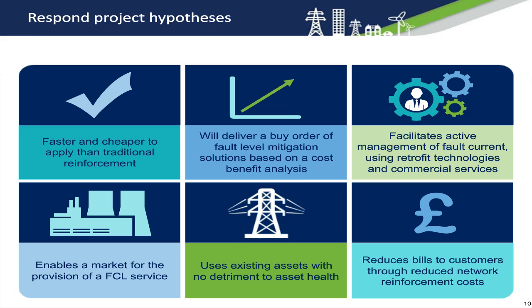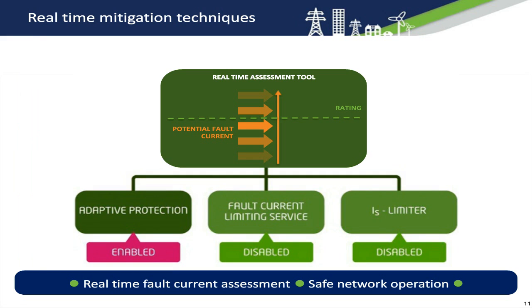When a fault level approaches or rises above the fault level rating of our network equipment, the fault level assessment tool, known as a FLAT, which is now embedded into our network management system, will enable or disable one of three innovative techniques designed to manage fault current. They are adaptive protection, the fault current limiting service, and the IS limiter. All three techniques, when enabled, respond after a fault, reducing fault current so that every item of network equipment operates safely.